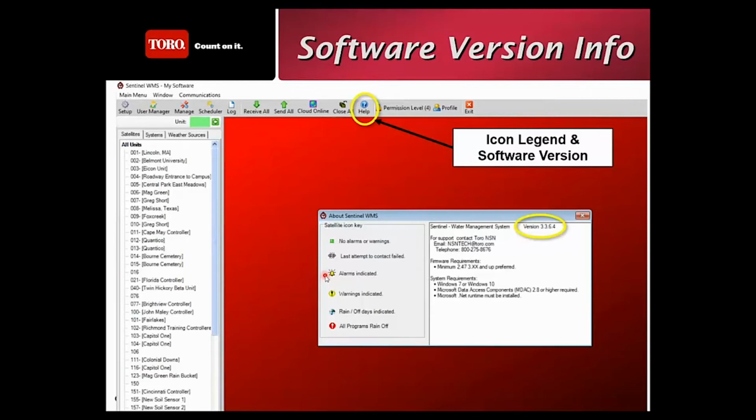It could be that there was a power cycle on the controller. It could be that there was a rain sensor and it tripped what's called an external alarm. It could be that you had a flow alarm. It could be that you had a bad solenoid. So there's multitudes of things. All it's doing is giving you, at a glance on the left side of the screen, and I don't have it with the screen capture I have, but you'll see it when I pull up the software. So it's an at-a-glance kind of look at, hey, you need to go check this.